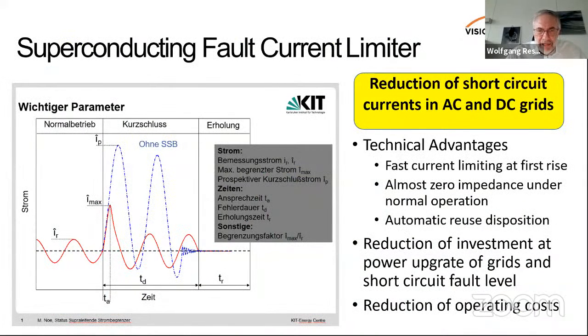There are also possibilities of doing a superconducting fault current limiter. That happens if the current is higher than the superconductor can carry. In this case, the superconductor leaves the superconducting state and becomes normal conducting, and because it has such a small cross-section, it then has a very high resistance, which limits the fault current. It can be used in AC and also in DC grids, which might be helpful for switching off DC currents.